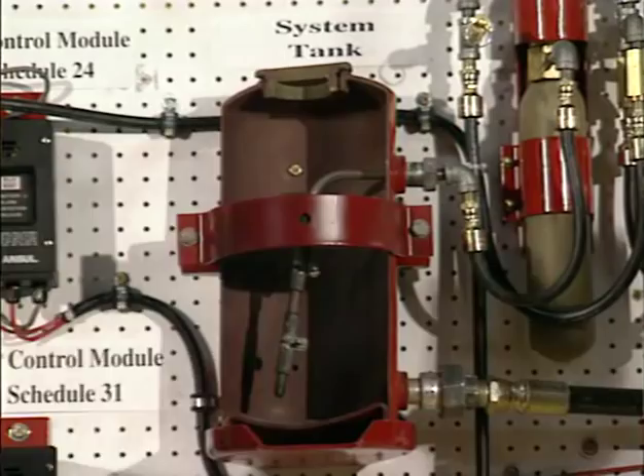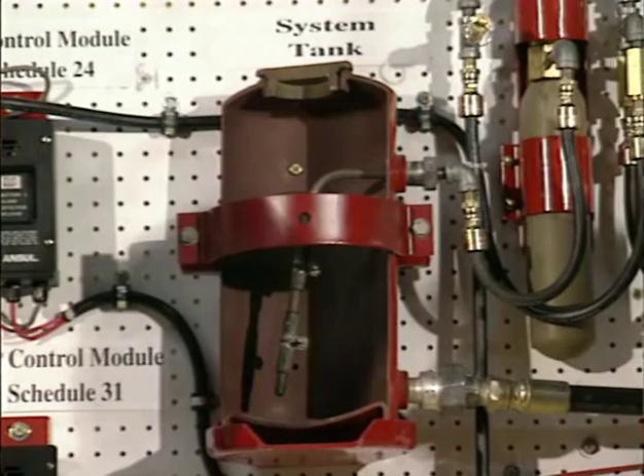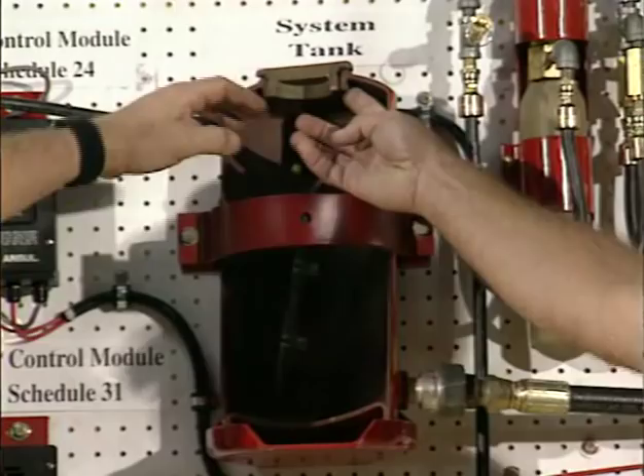Open up the top. Because of the chemicals settling as the vehicle moves, the chemical level should not be more than three inches below the mouth of that canister. The siphon tube only needs to come out if you can physically see damage, or for a hydrostatic test — you have to take it out when you hydro test them.